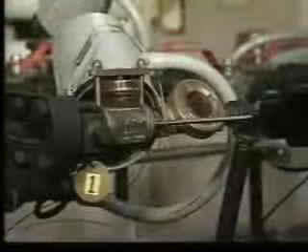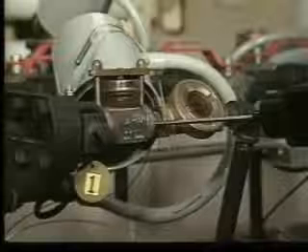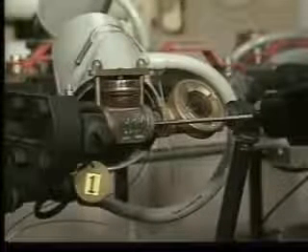The first traps we will test are intermittent traps. This is a disc trap. Listen for the disc trap's hold, discharge, hold pattern 4 to 10 times per minute.